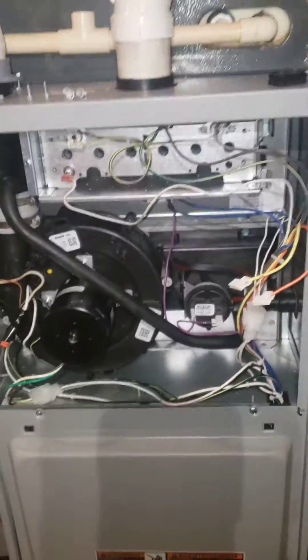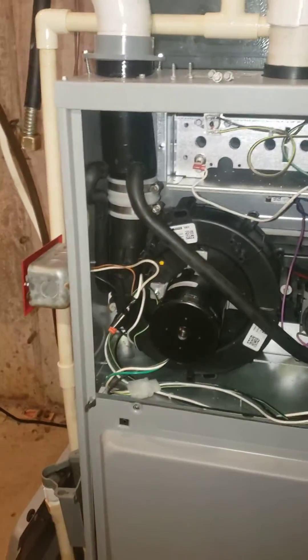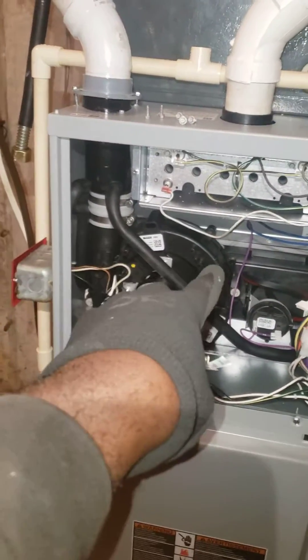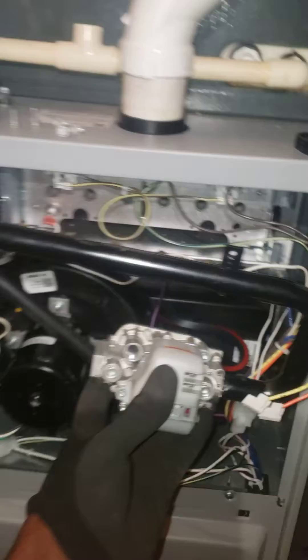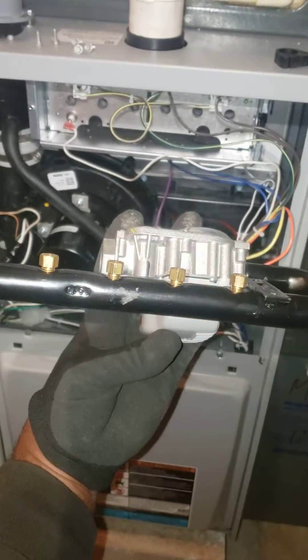All furnaces are shipped for natural gas applications. In this circumstance, if you do have a propane supply, I took the gas line out here, but you have to change the spring in the gas valve, and you also have to change the orifices. This is pretty much how it looks.